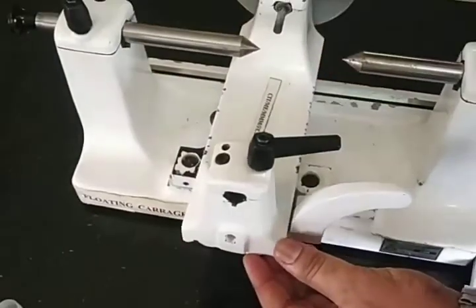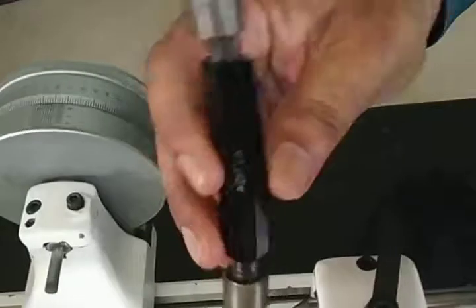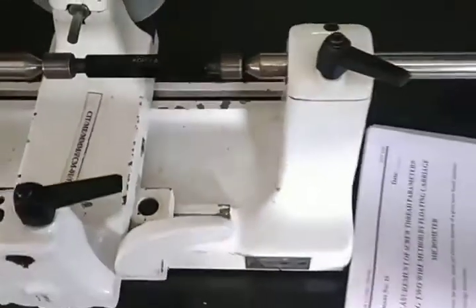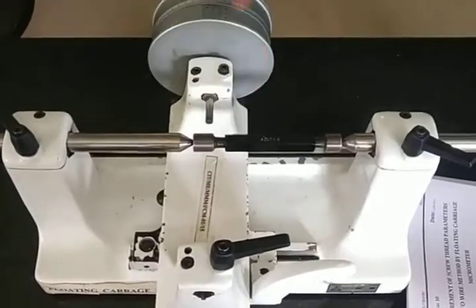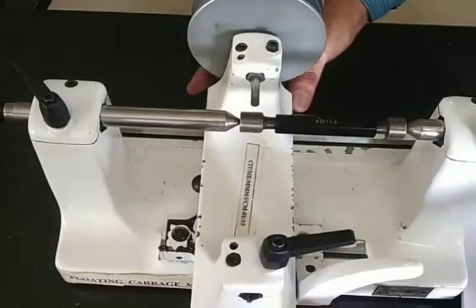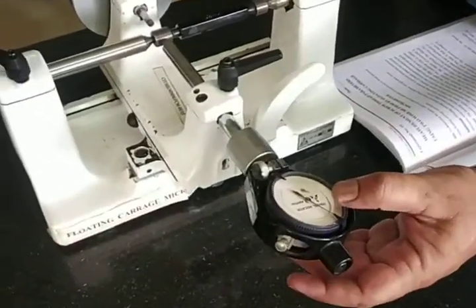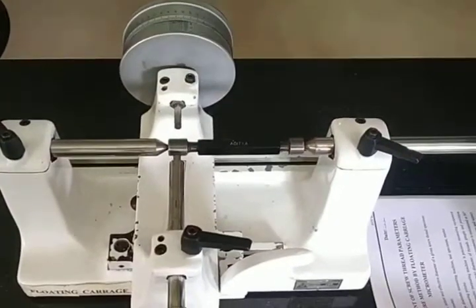The setup has two floats. When we mount the specimen, the axis of the specimen and the axis of the micrometer will be exactly perpendicular. The floats move to measure diameter and can also move along the axis. There is a fiducial indicator which is used to create a constant pressure throughout the experiment. If excess pressure is applied, the micrometer anvil or the component threads can be damaged. To maintain constant pressure, we use this fiducial indicator.